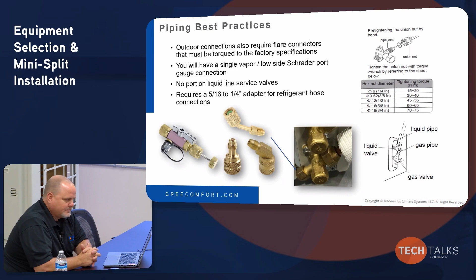And that's why I stress that suction line being bent properly, because that is your discharge line in heating mode. Exactly. And an oval bend is not the same as a 90-degree clean bend. Yep. It's just not the same. So hand bend this pipe, and you want to do that as minimally as possible. Don't use your elbow. It does not work. Even if you have brand new soft copper, it doesn't work.